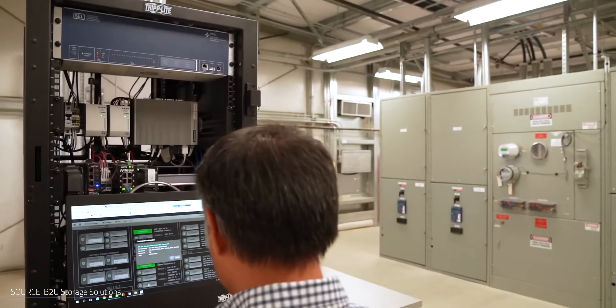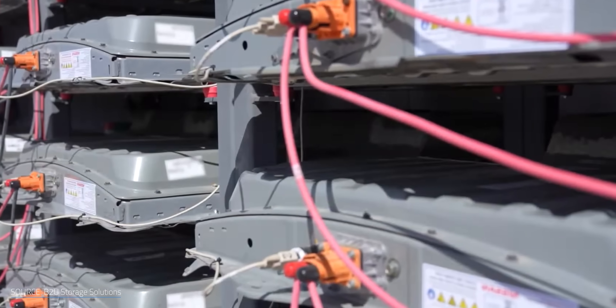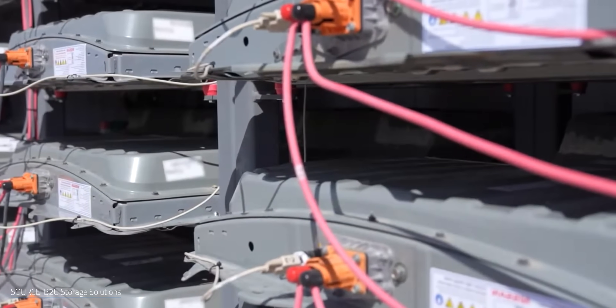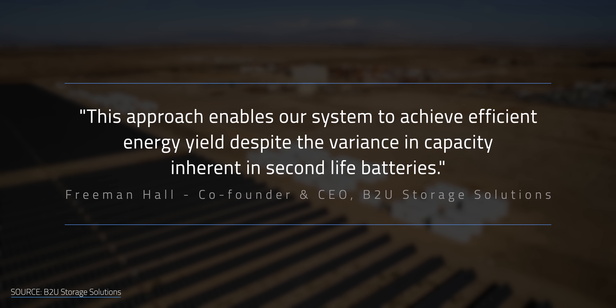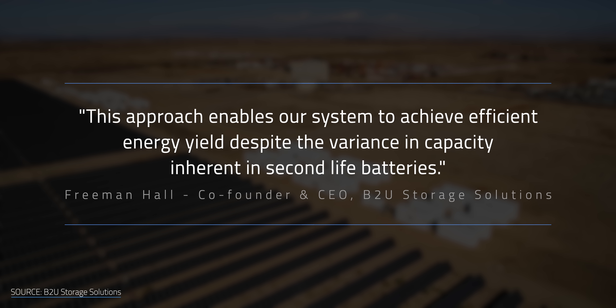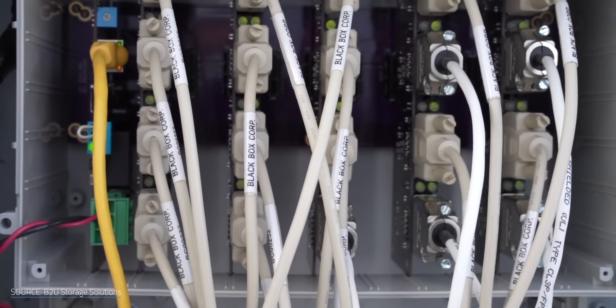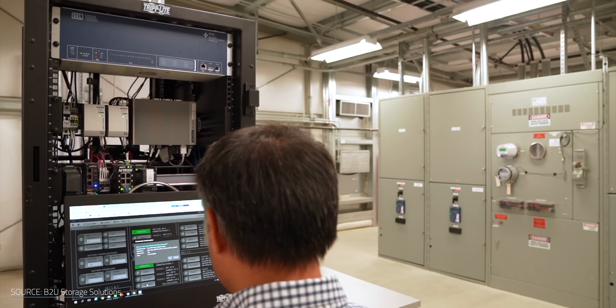It's here that B2U's biggest innovation comes into the picture. Their software, in tandem with their cabinet controllers, monitors all those battery variables during charge and discharge cycles. It can connect and disconnect the batteries as needed, allowing the older batteries to take a break before they drag down the performance of their buddies. B2U CEO Freeman Hall claims that this approach enables their system to achieve efficient energy yield despite the variance in capacity inherent in second life batteries. On the safety front, B2U's EPS cabinet controllers monitor the health of individual batteries and flag situations where there are potential problems. The operators can also set strict safety parameters, and if the battery deviates from these guard rails, the pack is automatically disconnected, allowing it to cool down and be dealt with rather than risking any kind of disaster.